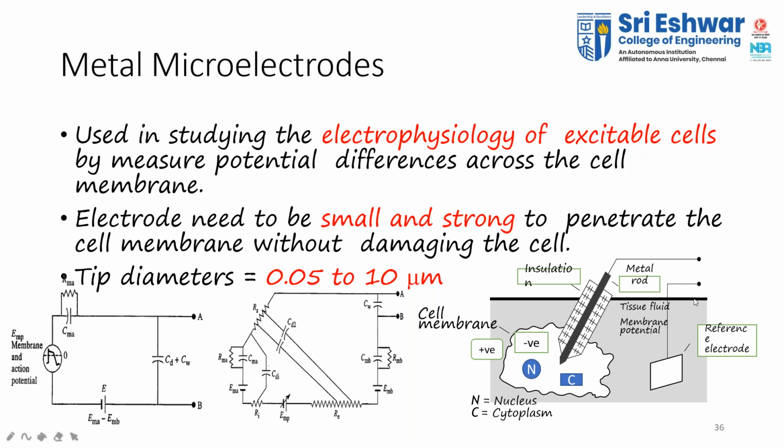have reference electrode. We can place the reference electrode over any part of the skin. So I am going to take the signal out of a single cell and compare it with my reference signal. Okay, this is given as input to my amplifier to boost my signal. This is the circuit, and here we have the equivalent of my metal micro electrodes. Your capacitors and resistors play a major role. The combination of RC network gives an equivalent circuit to my metal micro electrodes.